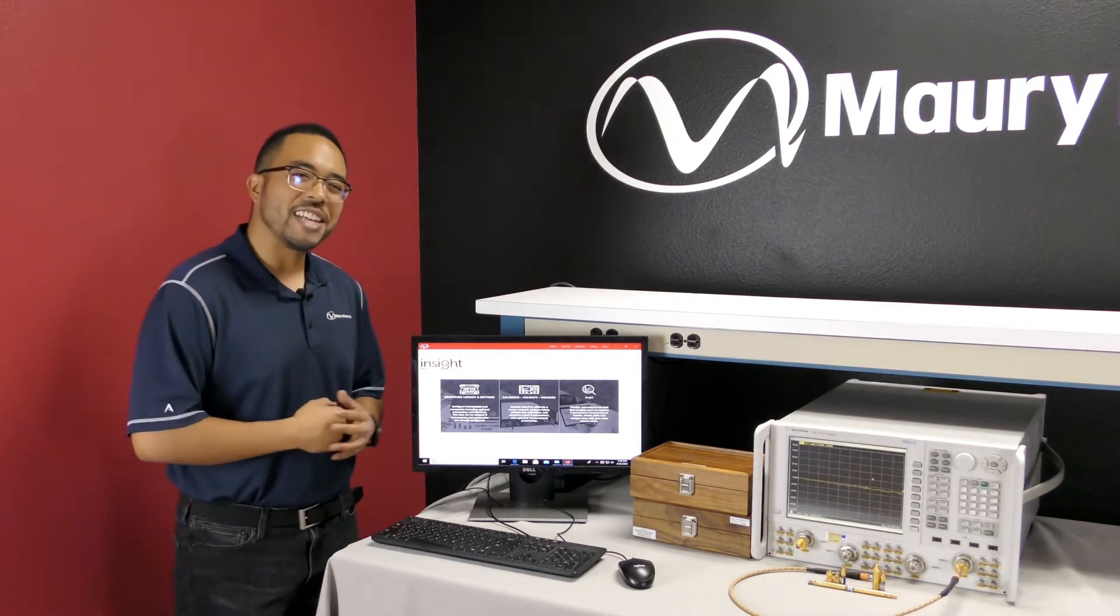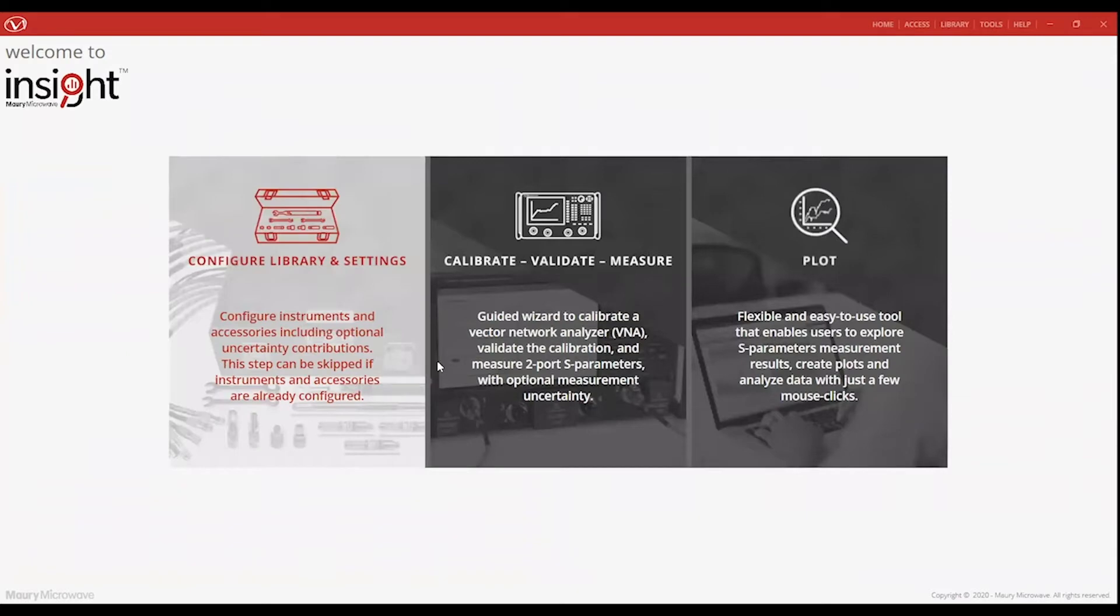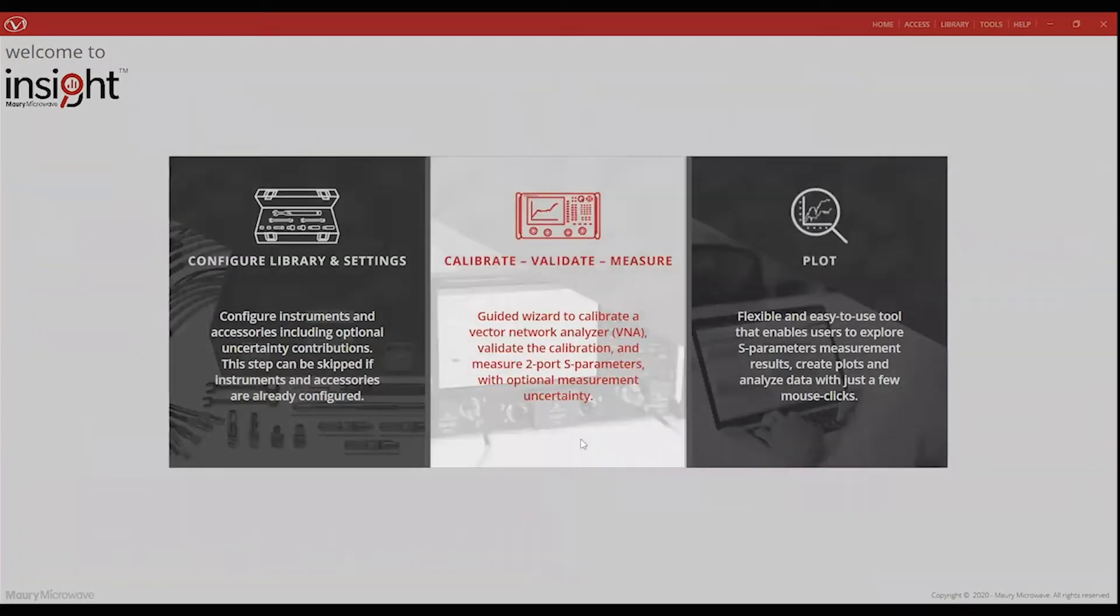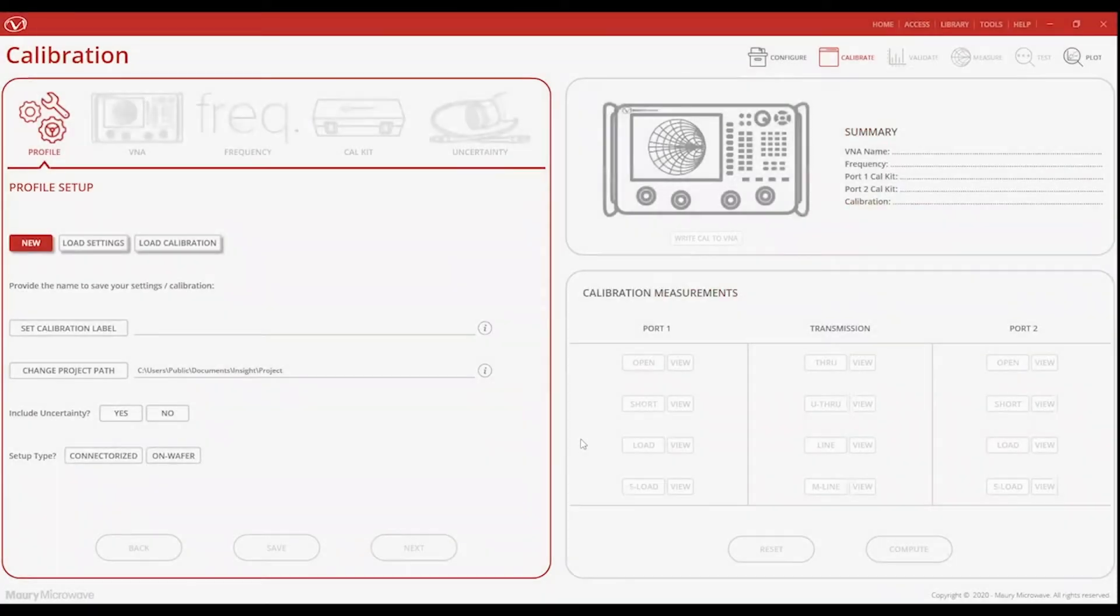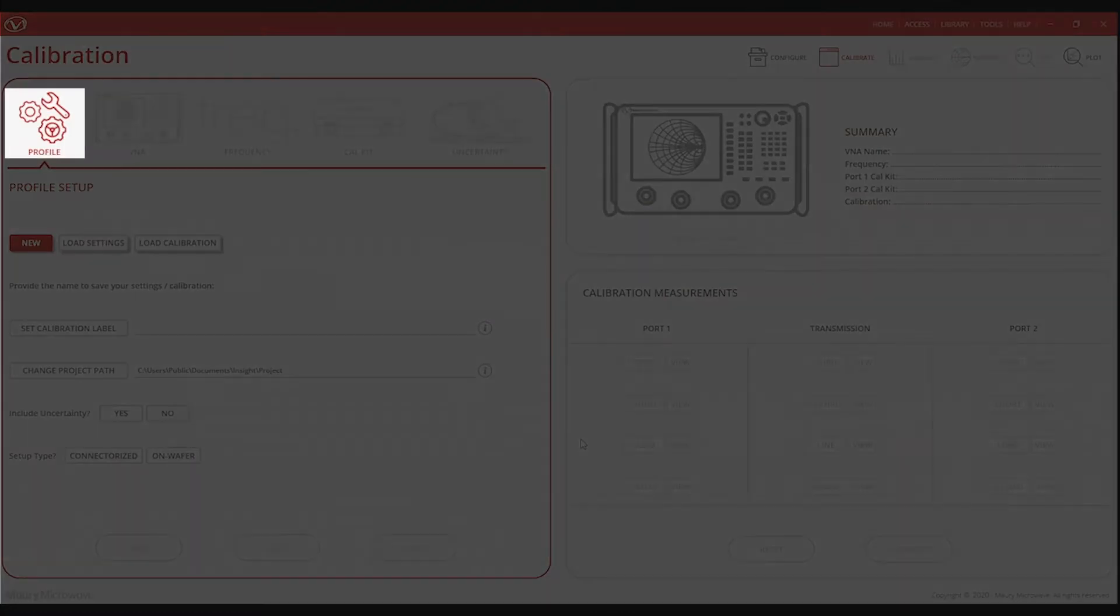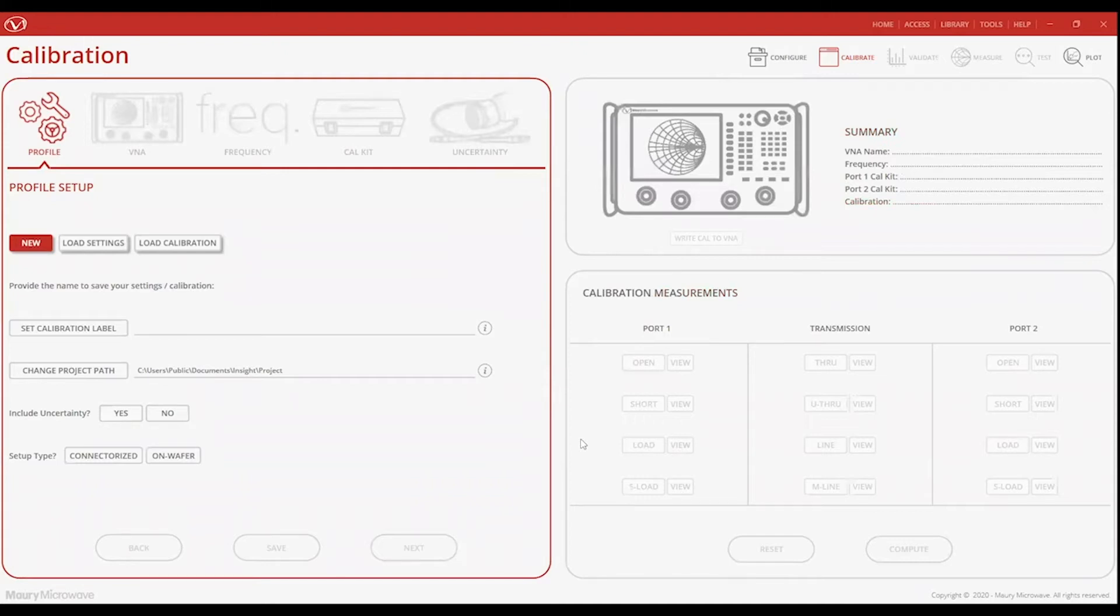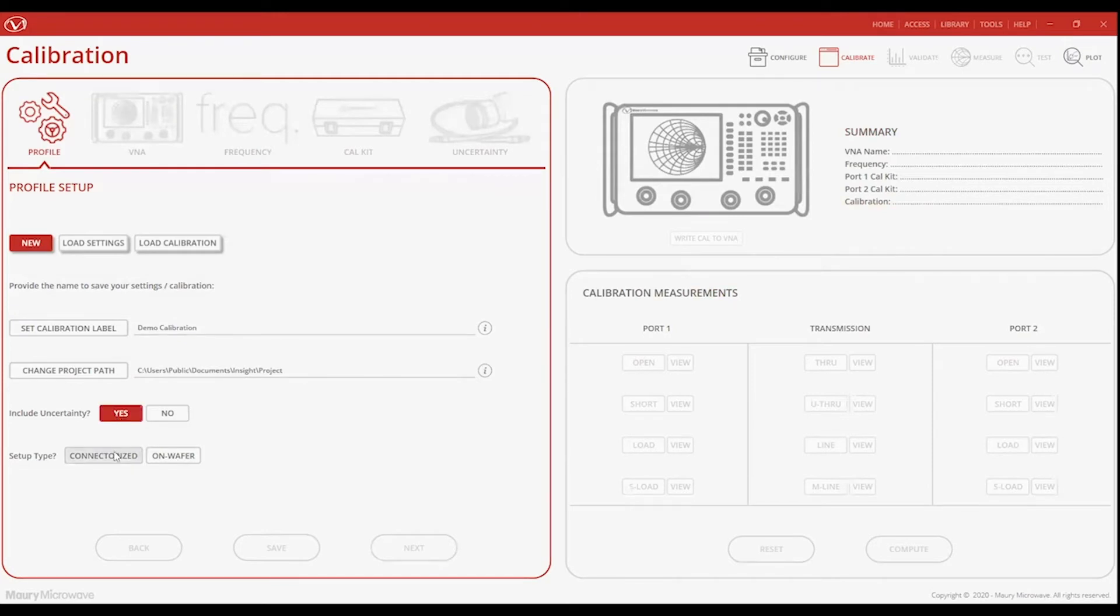Now, let's jump right into how Insight can help you validate your system. Today's demonstration will concentrate on calibrating a VNA and validating that calibration with utmost confidence. To begin, we'll select the Calibrate, Validate, and Measure module. As you can see, calibration starts with the Profile Setup tab. This tab allows us to create a new calibration project, which consists of all of our calibration settings. You also have the choice of loading a pre-saved setup or recall an existing calibration. This is incredibly useful in ensuring identical calibration settings are used each time and across multiple benches, resulting in a more consistent and repeatable calibration process. You can also choose whether to include measurement uncertainties or leave them out, and define whether the measurement setup will be connectorized or on wafer. For this demonstration, we're going to set up a new profile. In this case, we will include uncertainty as it is a critical part of our improved VNA calibration validation process. And lastly, we'll proceed with the connectorized setup.